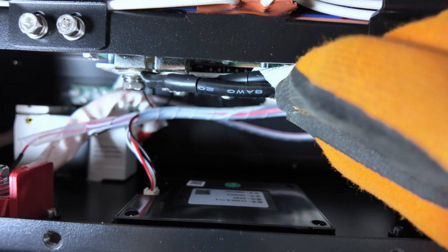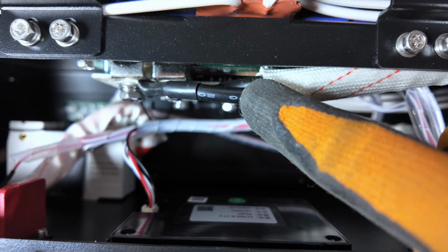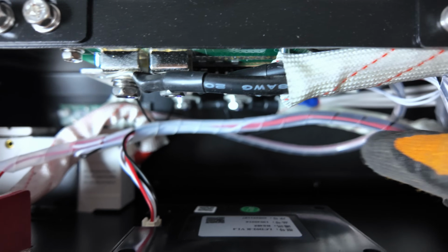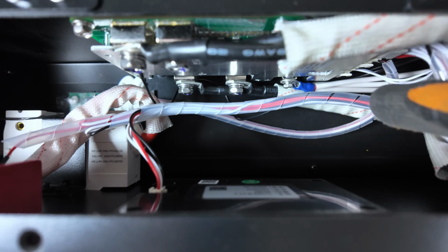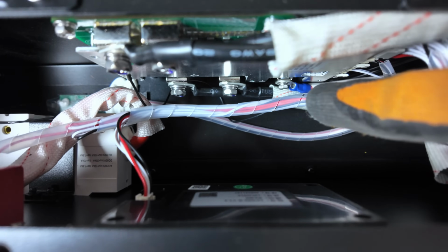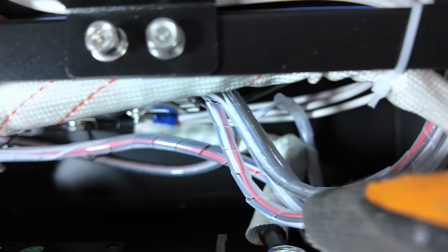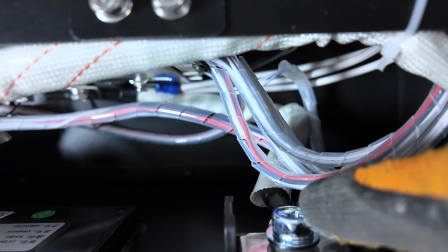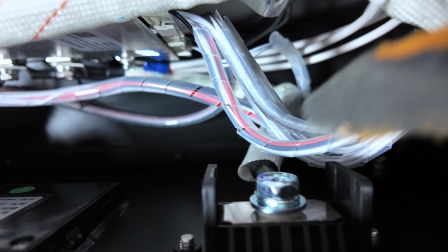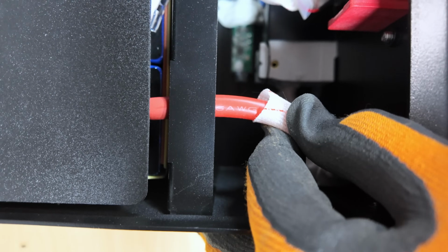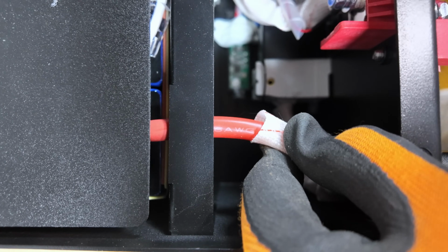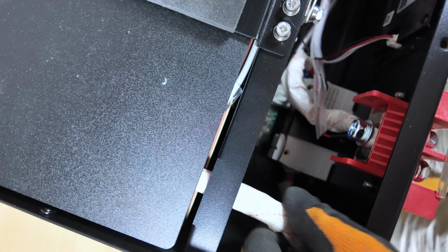Our negative cable, we have a double 8 gauge coming off of the cells to the BMS. And then looking down underneath, it looks like we have a similar double 8 gauge coming over and combining onto a single lug here on the negative. On our positive, is it going to show up? Yeah, 6 gauge wire. So again, I would like to see 4 gauge.